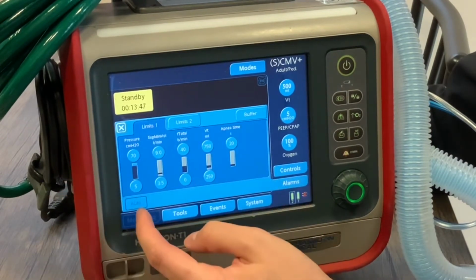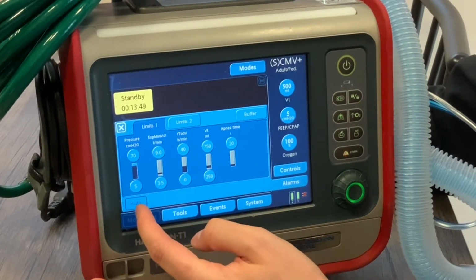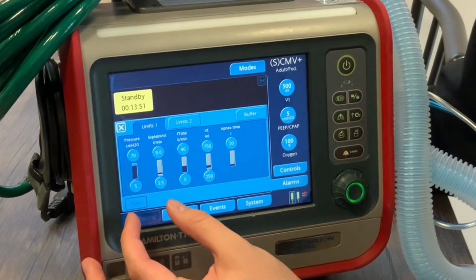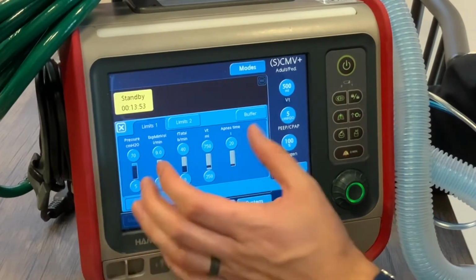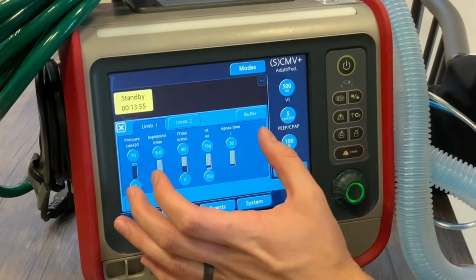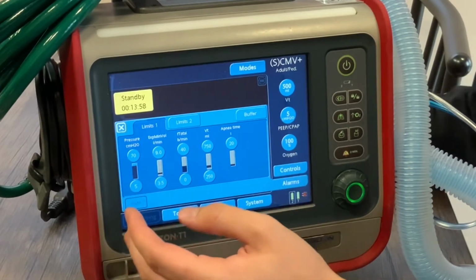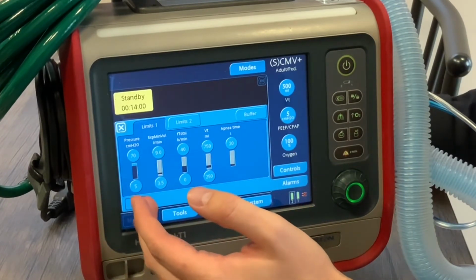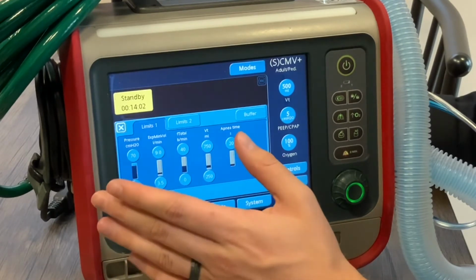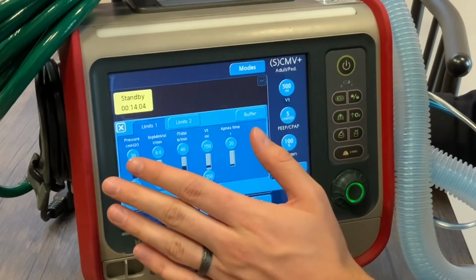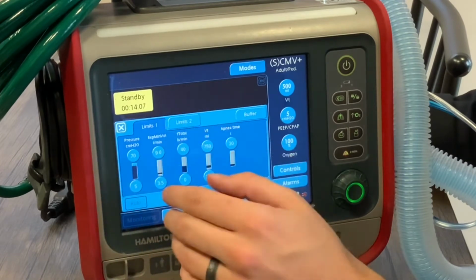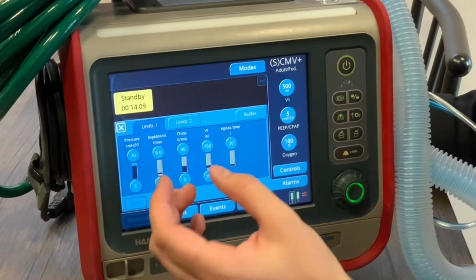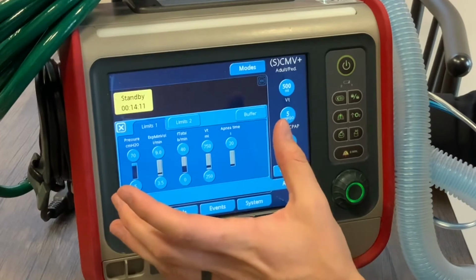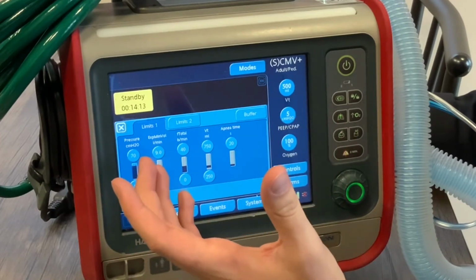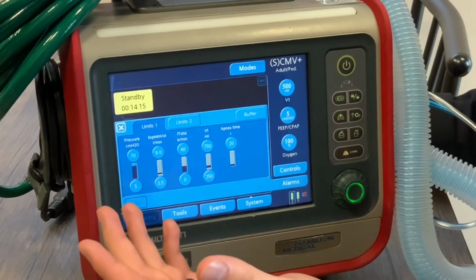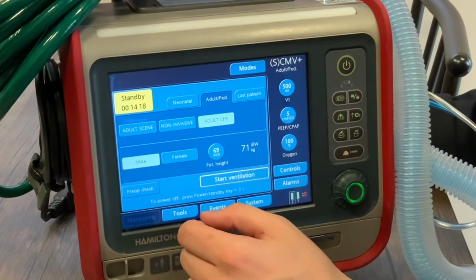There is this auto key that is grayed out because we're not ventilating, but I recommend against hitting the auto key because you really want to personalize your alarms to the individual patient. The auto key seems attractive, but if you use the auto key, it changes all the alarms at once. And so even if you just wanted to change the respiratory rate alarm because they were coughing, it's going to change all of the alarms. So you may not know that your tidal volume alarm went all the way down to 2 or something like that. So you have to be very careful when pressing the auto key.